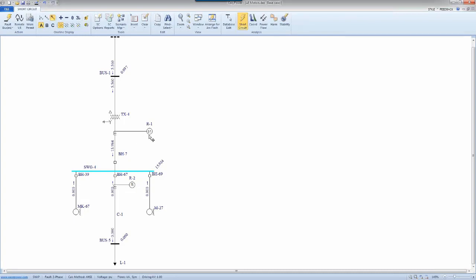Delta T hasn't got to that value, but we keep it in a memory, and I would explain how close I am to that trip time. And then I store all those values, I go to the second step. During that second step and third step and fourth step, I have a chance to update the fault currents, meaning that if I pass half cycle or 1-cycle and I move into 5-cycle area, I would update all my fault currents based on the time.